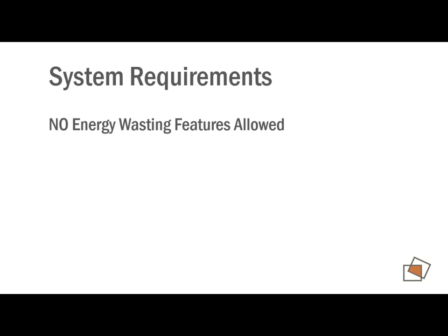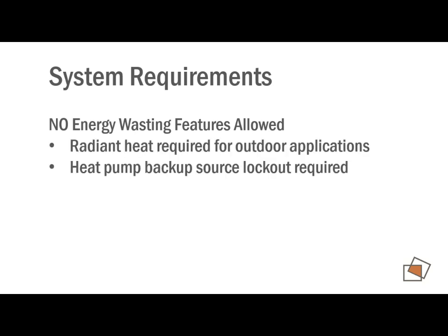Okay. And then there are energy saving features as far as our additional requirements. The other thing is they don't let you waste energy. So it pretty much boils down to these simple things. Don't run a heat pump at the same time as your electric heat. They want you to lock that system out. If you're doing outdoor heating applications, you need to be using radiant heat. You can't just blow air outside. 2012 doesn't have too many requirements associated with that.